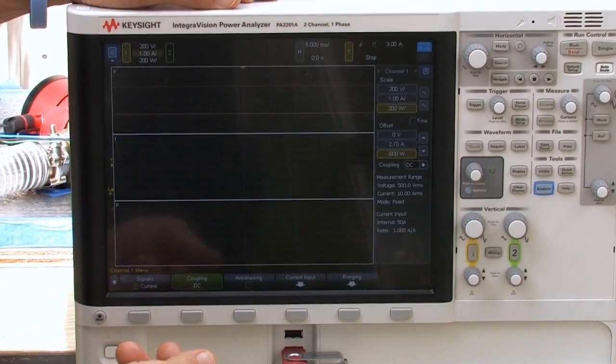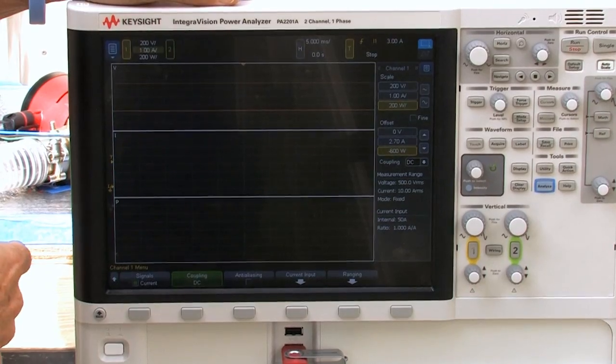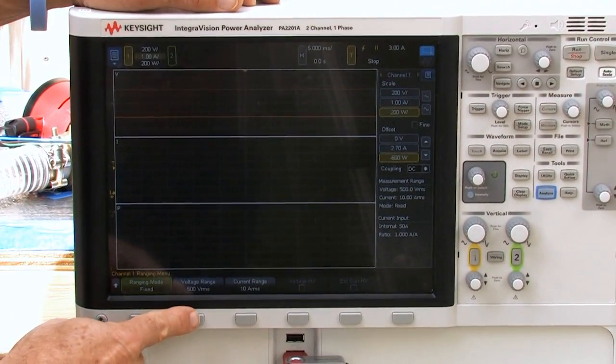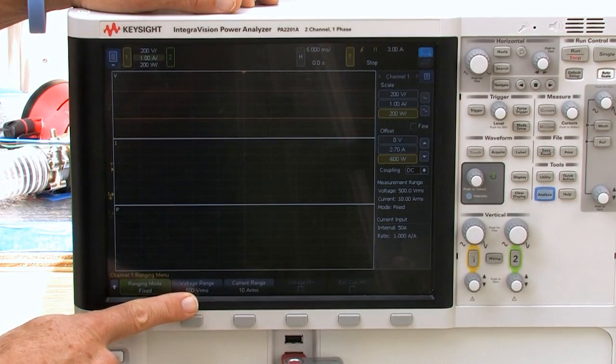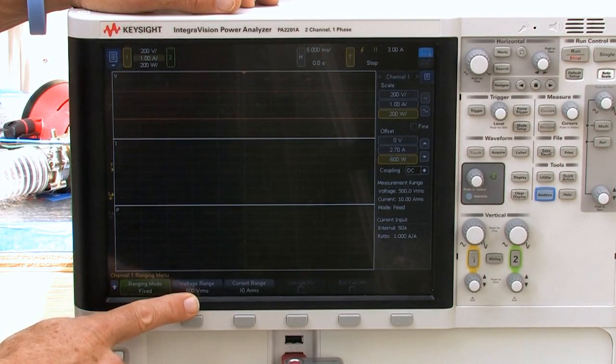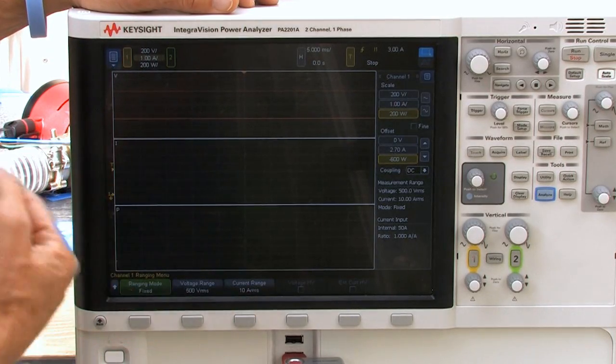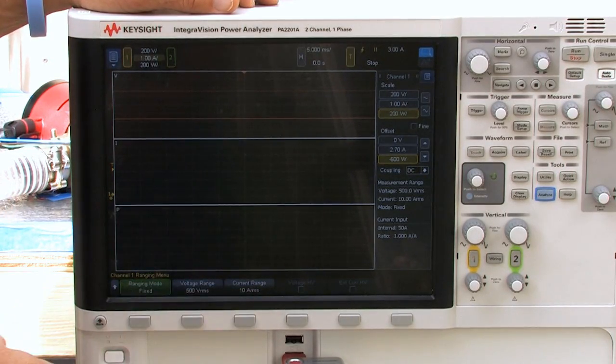First thing I want to do is just check on the ranging, so I'm going to hit range and check that we have 500 volts range set up and the 10 amp range. I'm expecting the current pulse to be somewhere between 5 and 10 amps, so we've got that set up.